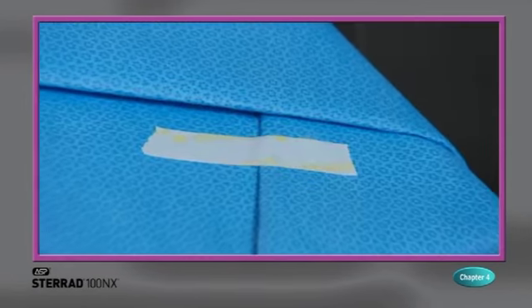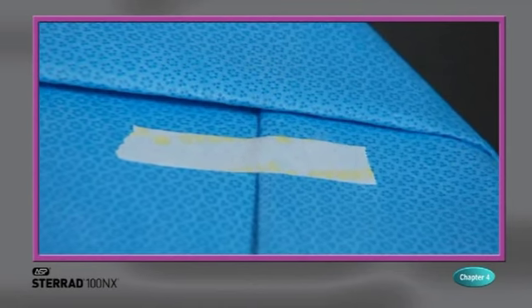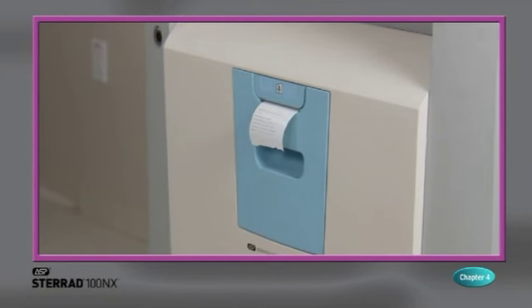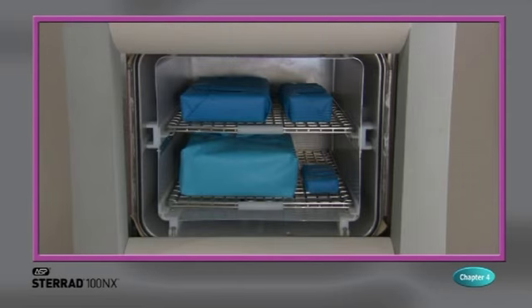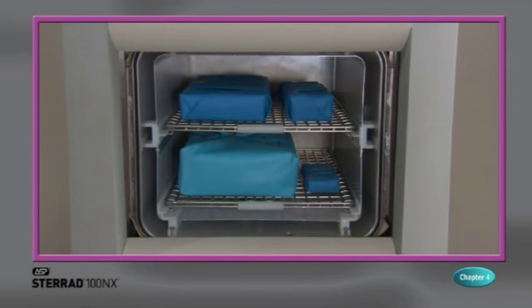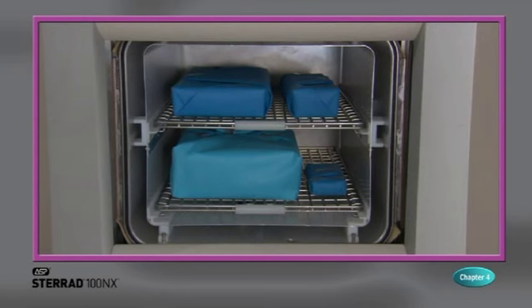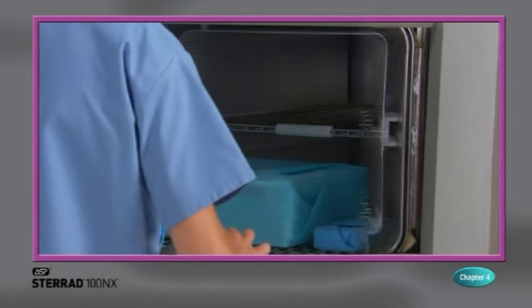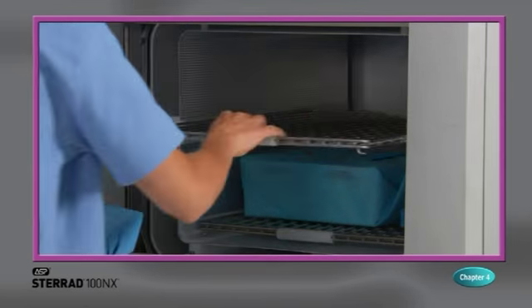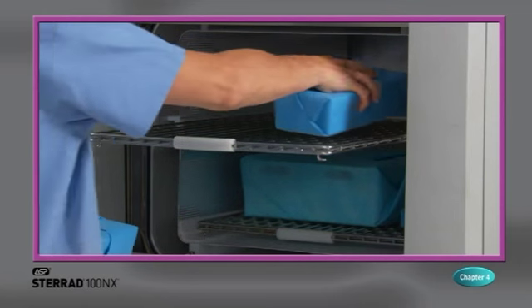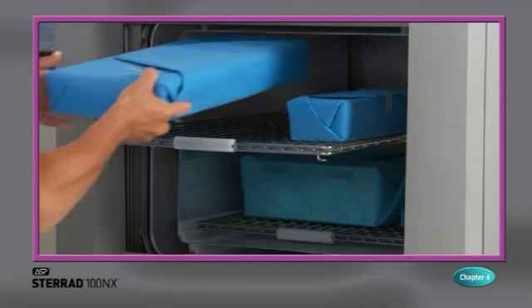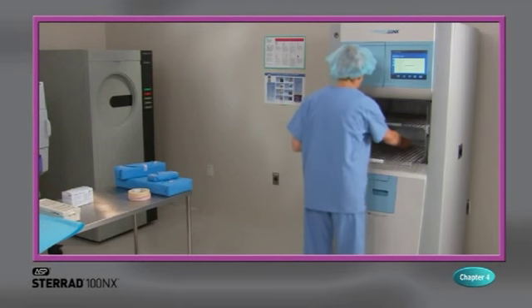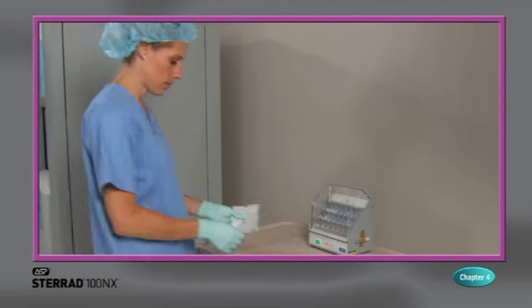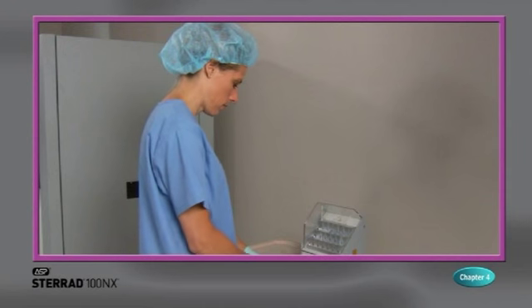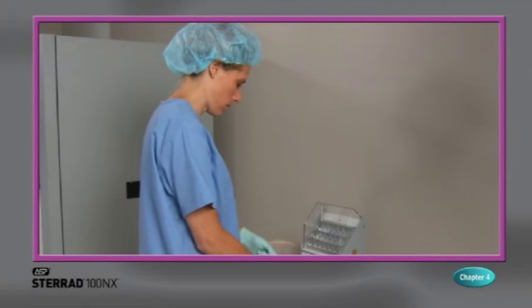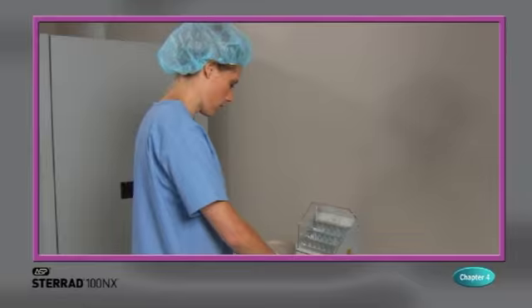After ensuring that the chemical indicators exhibit the correct color change and the cycle printout shows that all the necessary cycle parameters were met, the sterilized load is ready for immediate use or stored following your facility's policy. If the chemical indicators do not exhibit the correct color change, investigate the cause, repackage, and then reprocess the load. Remove the biological indicator from the load and process it per its instructions for use. Refer to the instructions for use included with the biological indicator to ensure its proper use.